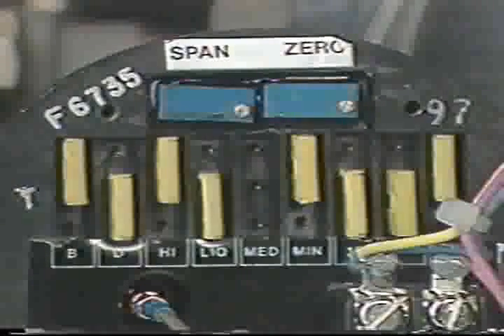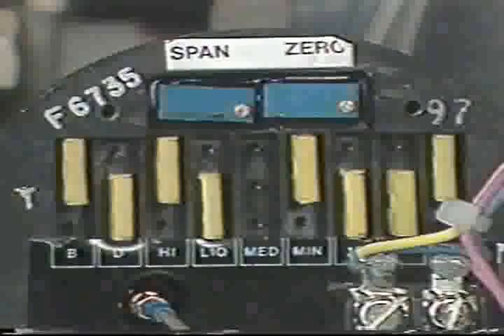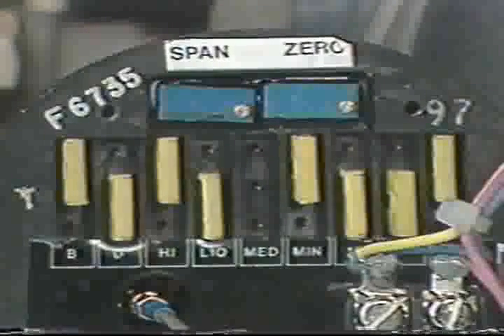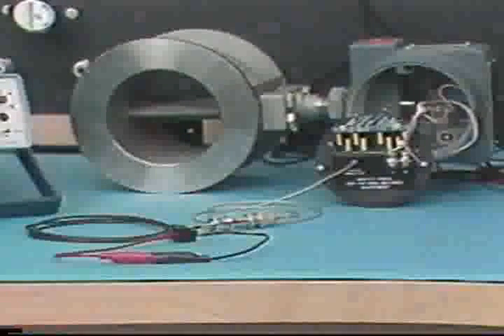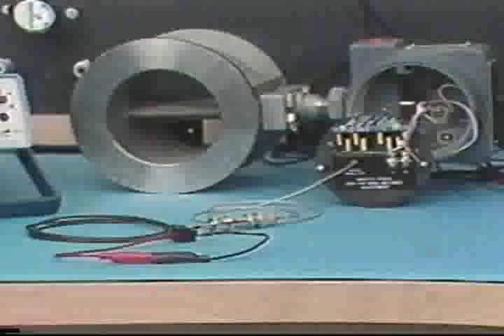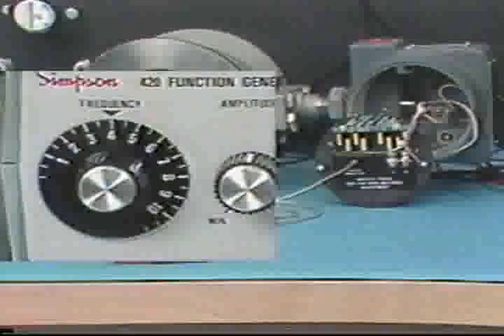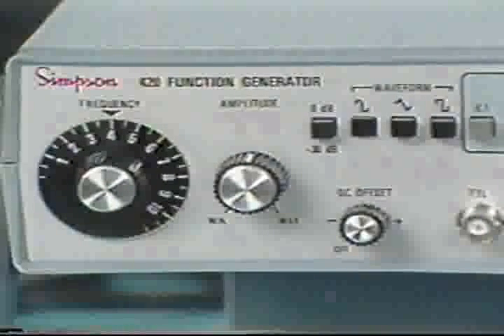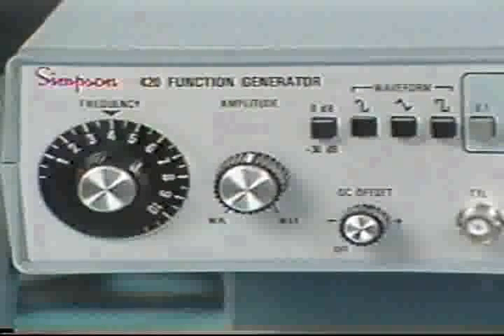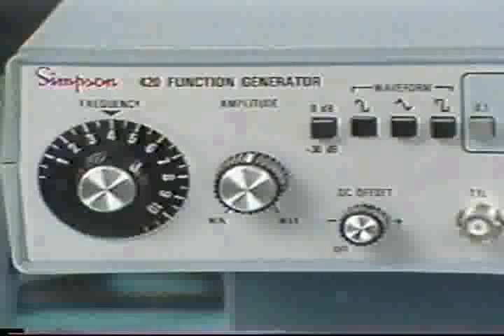Once the fine span adjustment has been completed, as indicated by a 20 milliamp reading on the output standard, the zero can be adjusted. Precautions should be taken to ensure that no stray pulses affect the zero adjustment. Here we've disconnected the frequency generator and the signal lead has been connected to the shield of the coaxial cable. Zero is adjusted at the low range value, so the generator must be set to the appropriate setting following the fine span adjustment. The zero is adjusted until the output signal matches the input signal at the lowest input value.